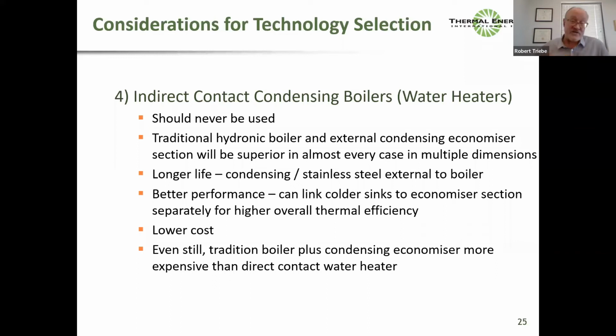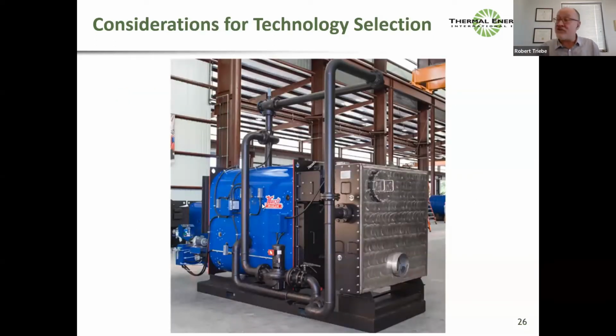In my opinion, we should never be installing condensing boilers anymore. If anybody wants to achieve condensing efficiency on their hot water circuit, you're much better with a traditional hydronic boiler and an economizer, or you're better with the direct fired water heater. But an indirect condensing boiler, I honestly can't see a situation where I would recommend one. And here's just an image of what this is: a traditional hydronic boiler with the economizer external. So you can see it's quite simple.